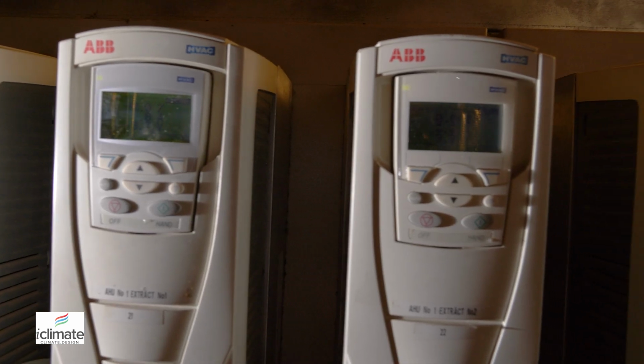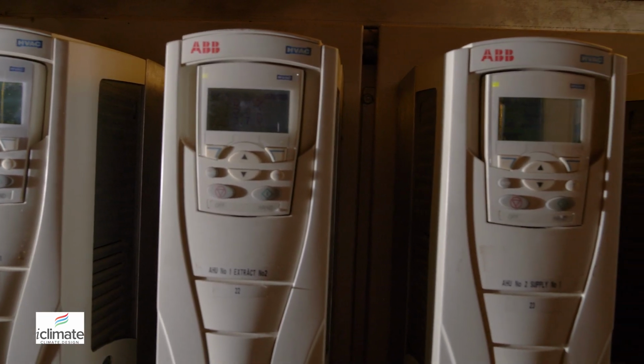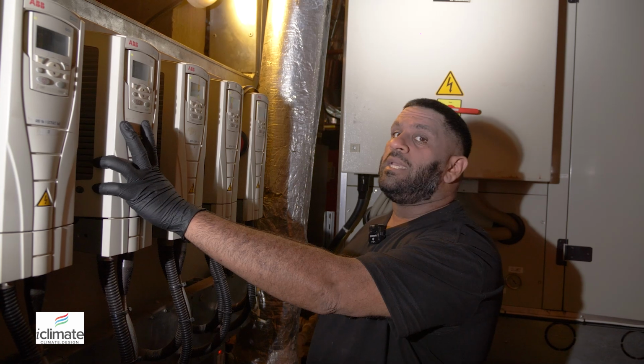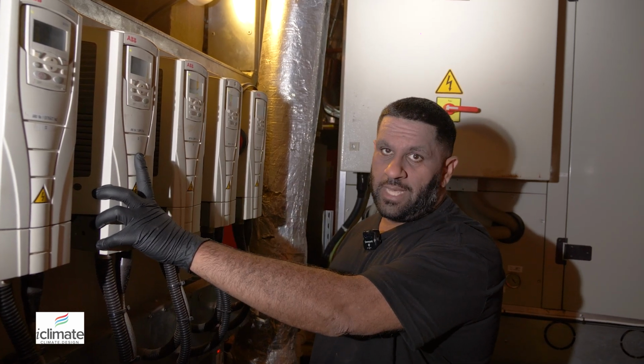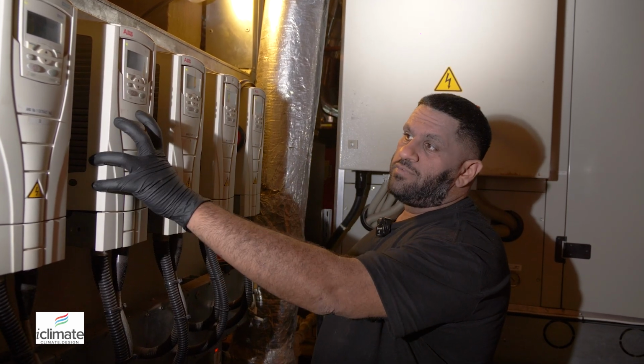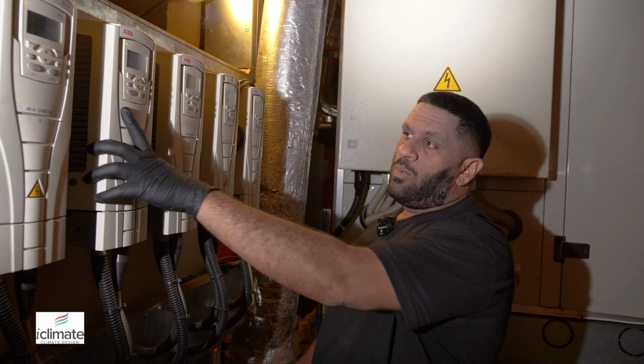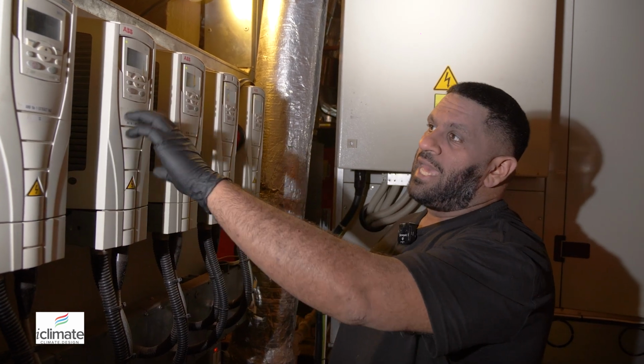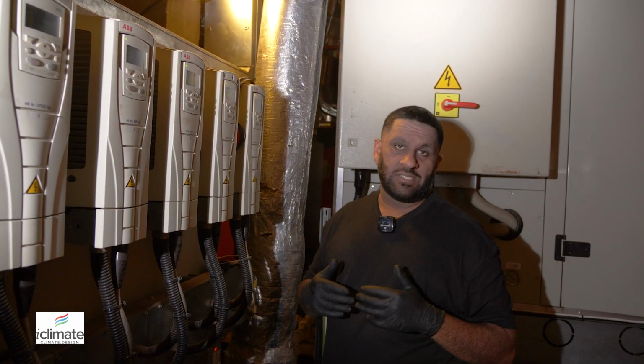These are not heads. These are inverter modules. So this is essentially the inverter PCB, but for a commercial ventilation application. Okay, so this is what drives the very large industrial fans, whether they be supplies or extracts, and it controls their speed essentially according to what's required. These are essentially a soft starting mechanism as well.